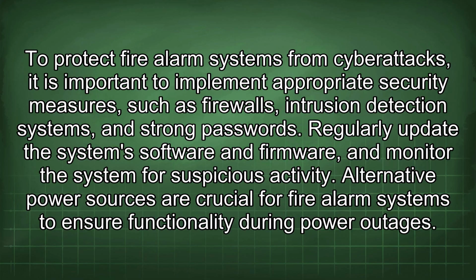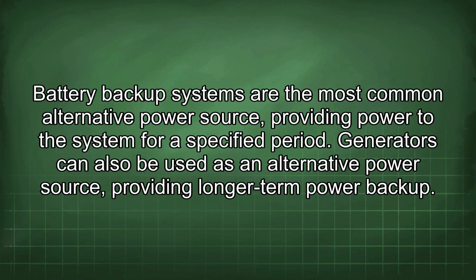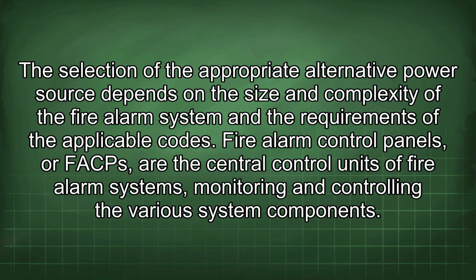Alternative power sources are crucial for fire alarm systems to ensure functionality during power outages. Battery backup systems are the most common alternative power source, providing power to the system for a specified period. Generators can also be used as an alternative power source, providing longer-term power backup. The selection of the appropriate alternative power source depends on the size and complexity of the fire alarm system and the requirements of the applicable codes.